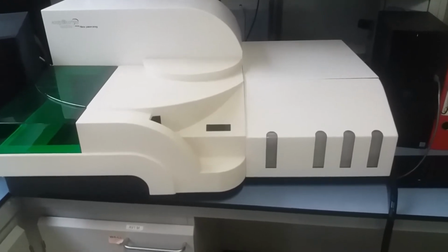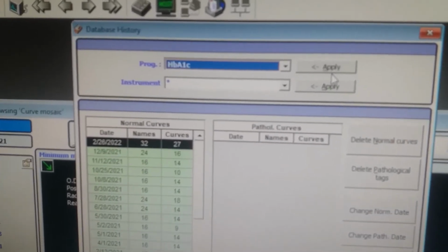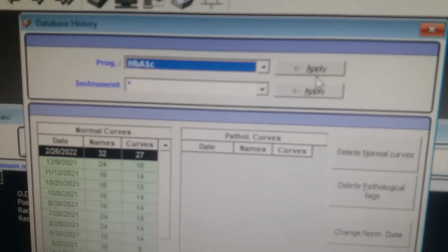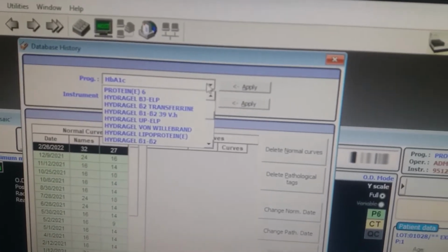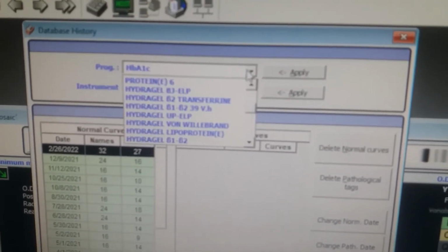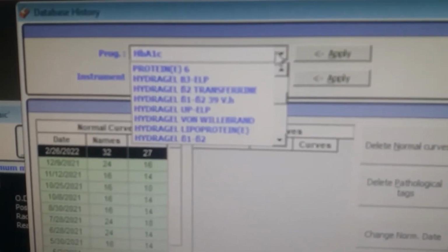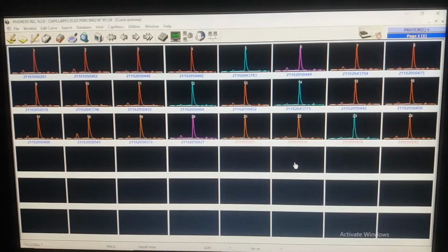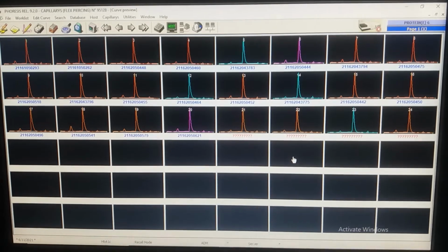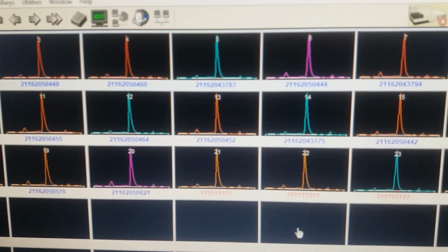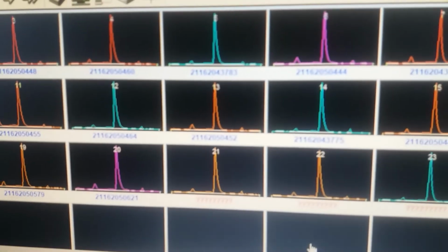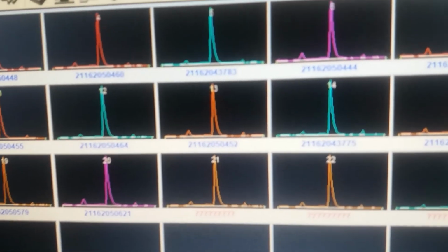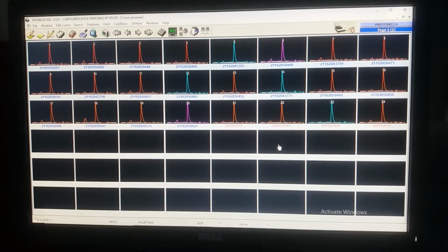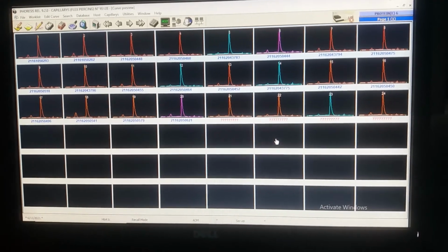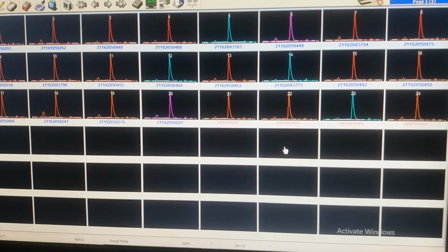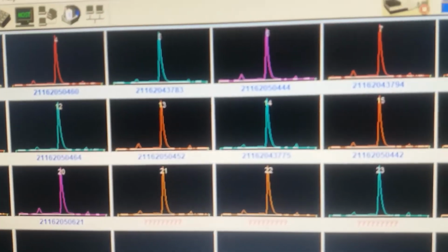When we see the procedure for the analysis of serum protein, the Capillarys 2 Flex Piercing system is a multi-parameter instrument for serum protein analysis on 8 parallel capillaries in the following sequence. First, there is barcode reading for sample tubes, for up to 8 tubes and sample racks, followed by sample dilution from primary tubes into dilution segments, and capillary washing takes place, then injection of diluted samples, and migration under constant voltage controlled by Peltier effect for about 4 minutes. Detection of serum protein is done by directly scanning at 200 nanometer wavelength, and electrophoretic profiles appear on the screen of the system.